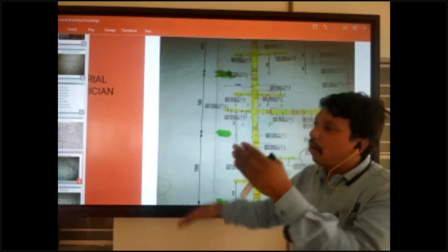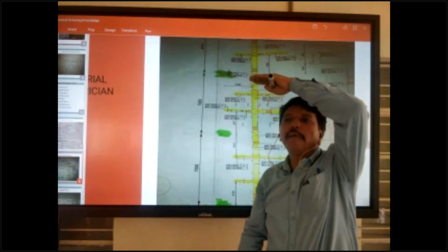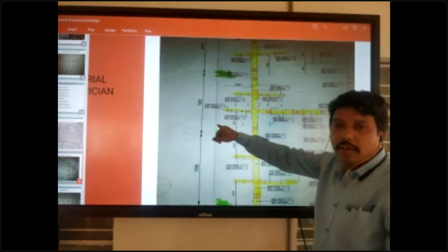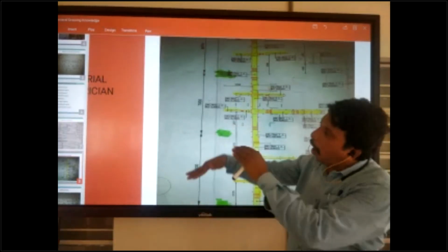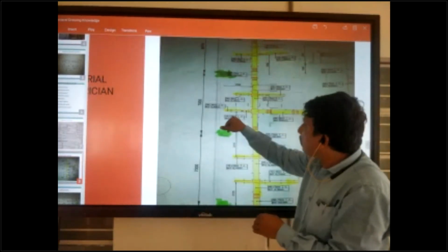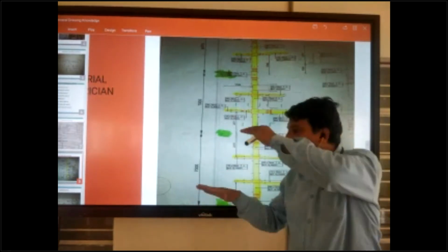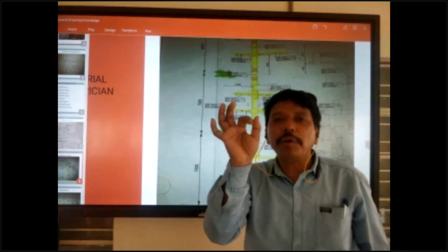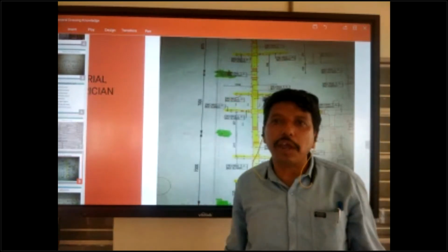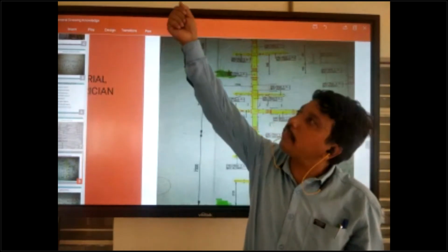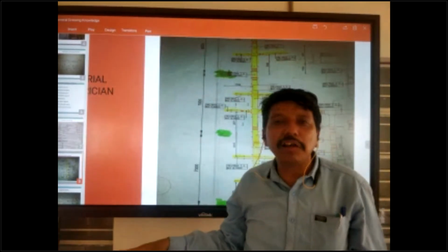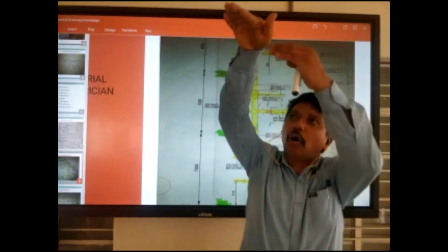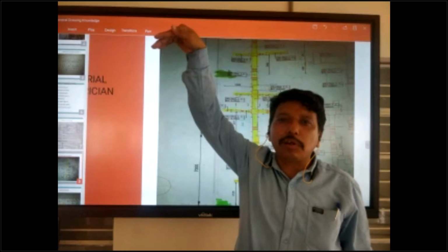The height level comes plus or minus from FFL, finishing floor level. So plus written means it comes above the finishing floor level. If minus is written here, this means it comes below the finishing floor level. So measurement always comes from FFL, finishing floor level, anywhere, not measured from the ceiling downward. You should measure from the finishing floor level, because your ceiling and your slab are not at a good level.